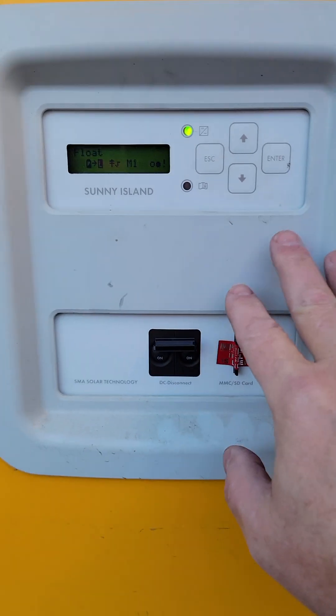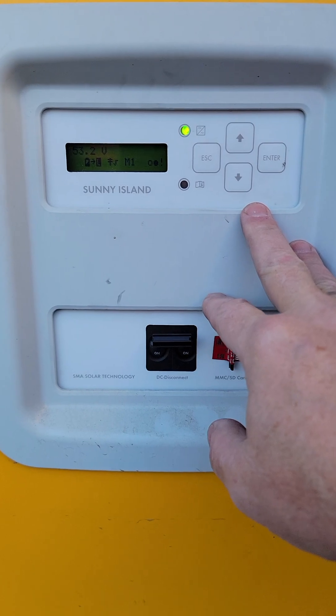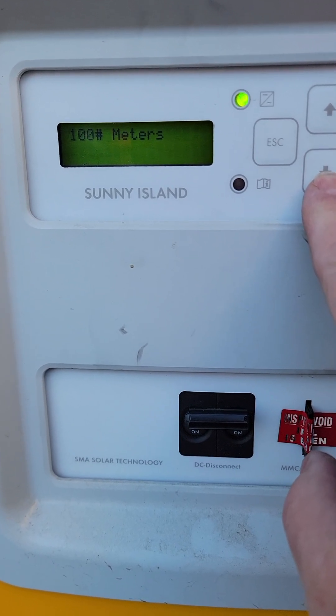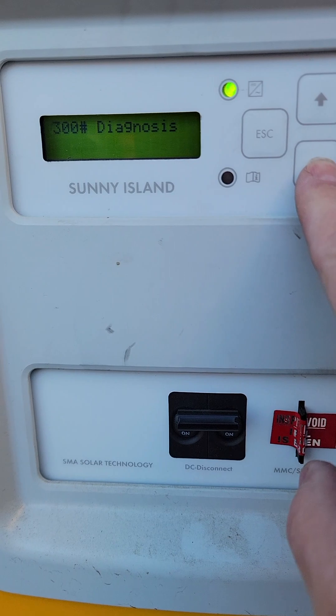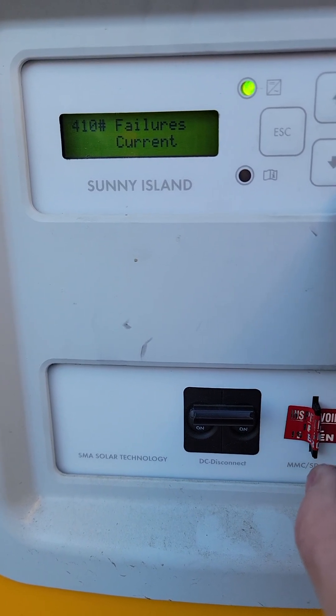But in this case, I don't want to power cycle the power to my house, because this is currently feeding my home. So I'm going to navigate the menus — I'll hit the down arrow. There's meters, settings, diagnosis, and then here: failure event. If I go into failure event, I have options in here, which is menu item 410.